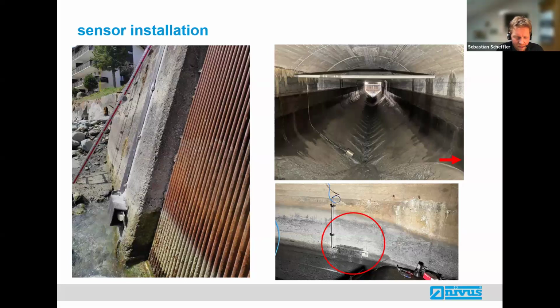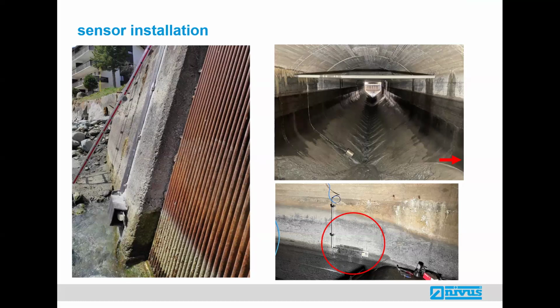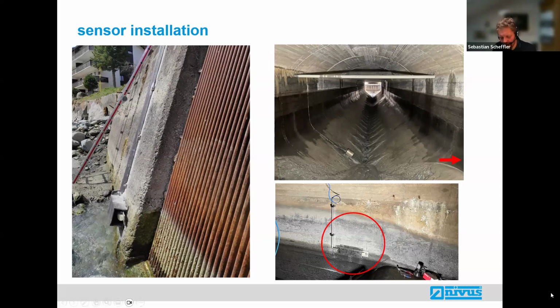An optical sensor means with laser, or with turbidity, with light. I think he is asking about some other application of sediment measurement, like an OBS sensor - I don't know if that sensor is for sediment measurement or not. Well, I think right now there are three different methods on the market to measure concentration: by turbidity, by Coriolis measurement, and by backscattering with ultrasound. The big disadvantage of turbidity sensors is that you have to clean them every few weeks, and you have to calibrate them every few weeks. That's the difference. Or what do you mean?